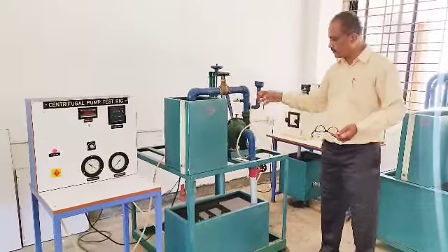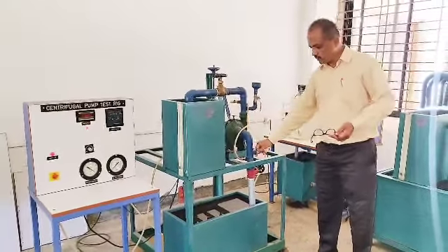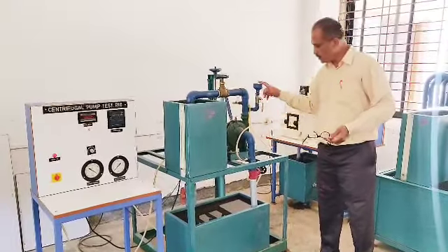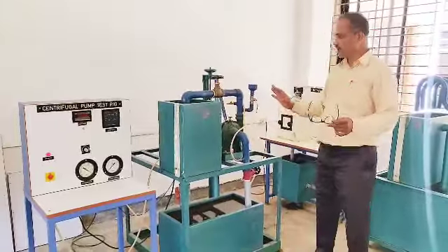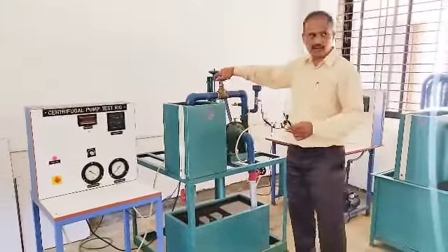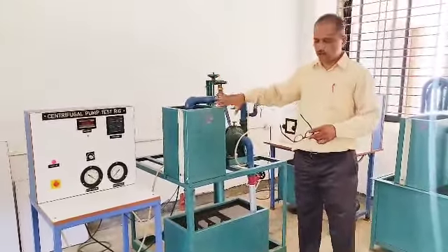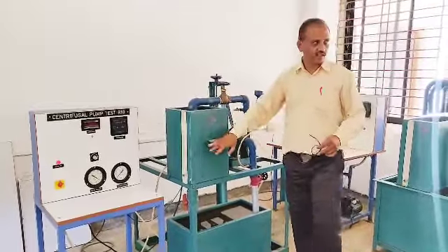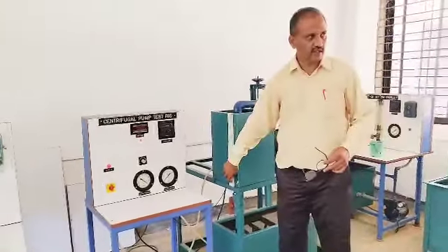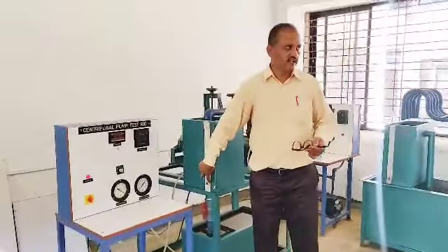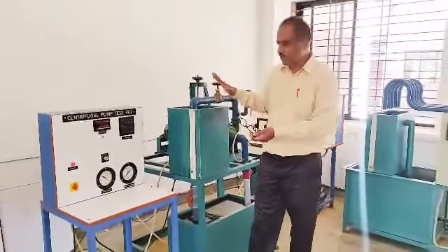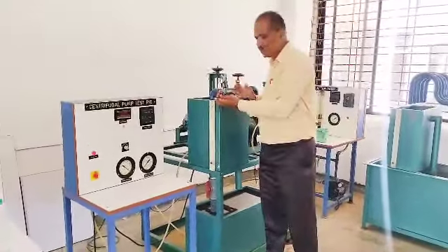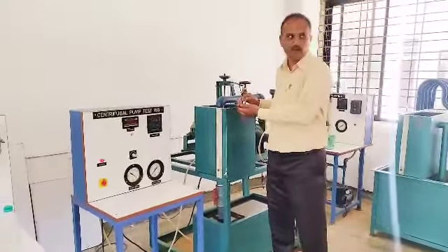And this is for priming. When I want to start the pump, there will be air in this, so I will put water here so that I can prime the pump. This is the experimental setup, and this is a valve, so I can control the various flow rates. And this is a measuring tank where I have a scale, and I will take the time required for a 10 cm rise. The dimensions of the tank are known, so I can find out the discharge. This scale and tank are meant to find out the discharge flow rate.